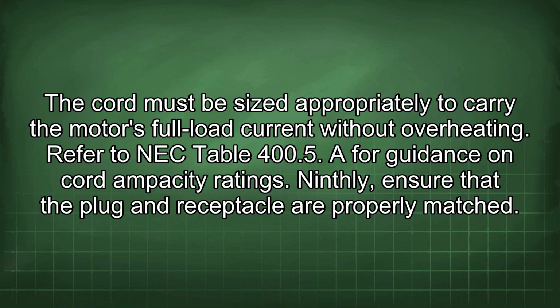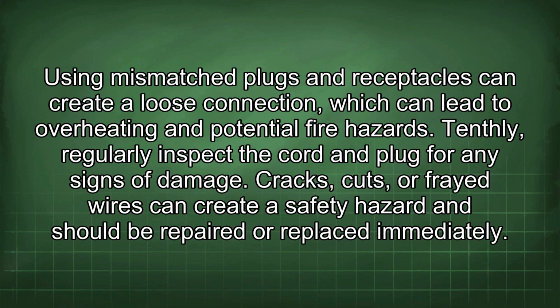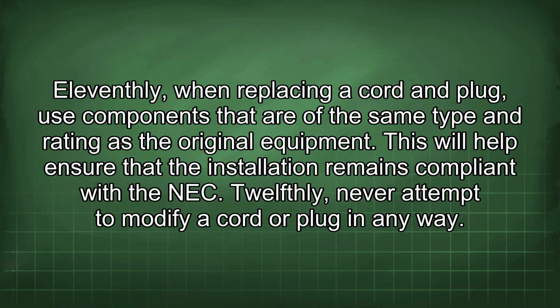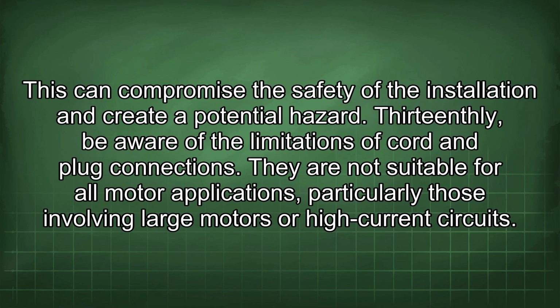Ninthly, ensure that the plug and receptacle are properly matched. Using mismatched plugs and receptacles can create a loose connection, which can lead to overheating and potential fire hazards. Tenthly, regularly inspect the cord and plug for any signs of damage. Cracks, cuts, or frayed wires can create a safety hazard and should be repaired or replaced immediately. 11thly, when replacing a cord and plug, use components that are of the same type and rating as the original equipment. This will help ensure that the installation remains compliant with the NEC. 12thly, never attempt to modify a cord or plug in any way. This can compromise the safety of the installation and create a potential hazard.